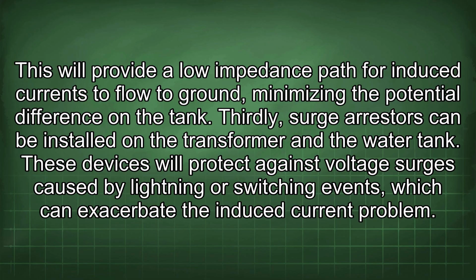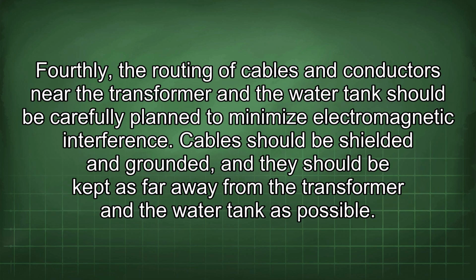tank. Thirdly, surge arresters can be installed on the transformer and the water tank. These devices will protect against voltage surges caused by lightning or switching events, which can exacerbate the induced current problem. Fourthly, the routing of cables and conductors near the transformer and the water tank should be carefully planned to minimize electromagnetic interference. Cables should be shielded and grounded, and they should be kept as far away from the transformer and the water tank as possible.